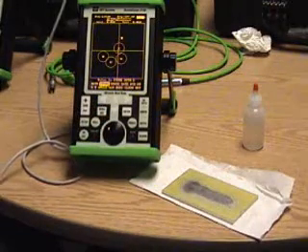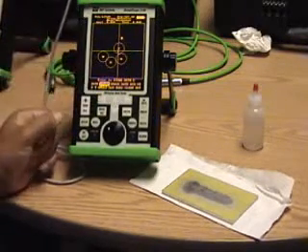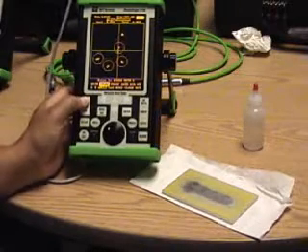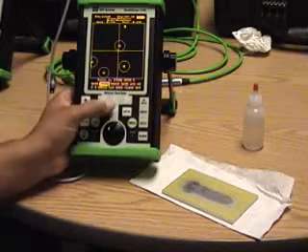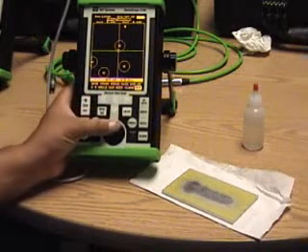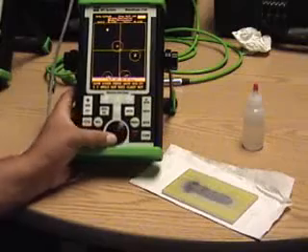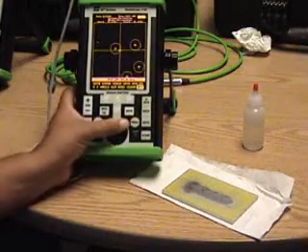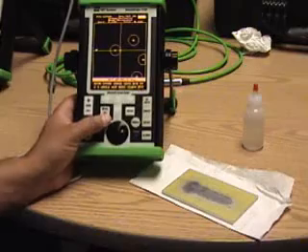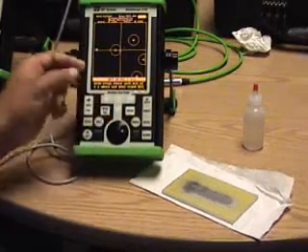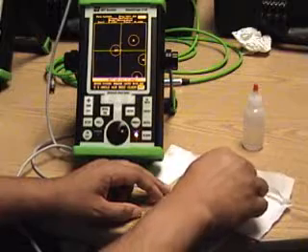Now, I have located all the dot positions. What I want to do now is set our gain and rotation to provide the best separation of all the dot indications. First I'll start off by introducing some gain. It's at unity gain. You'll see that the dots move away from each other based on the gain settings. I also will want to rotate, and we are rotating around the center. If you notice, we have our indications in various quadrants.